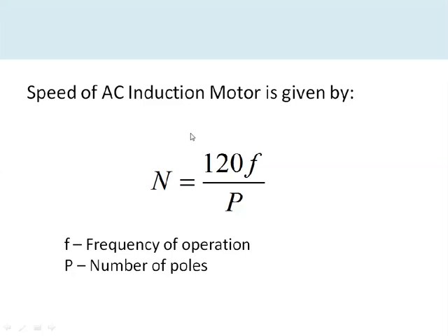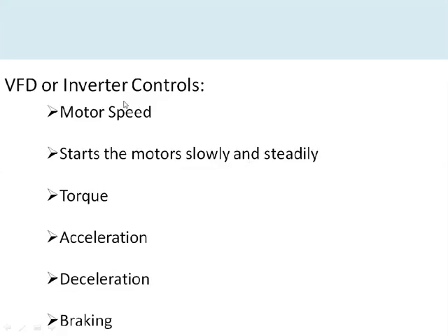The speed of an AC induction motor is given by N = 120f / P, where f is the operating frequency and P is the number of poles. Since the number of poles is fixed for a particular motor, in order to vary the speed of the induction motor, the frequency needs to be varied. This is done using the Variable Frequency Drive, also known as an inverter.